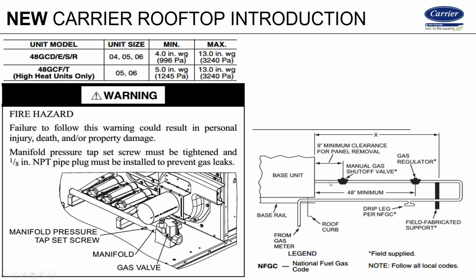When you put these regulators right next to the unit, in the winter when it's extremely cold, that exhaust, as the moisture freezes, it dissipates out and can fall right on top of the vent of the regulator. So you need to either keep your regulator out here or hook a tube up to the vent port and run that somewhere away from the exhaust from the unit. That goes for all units. Matter of fact, it goes for all manufacturers because a lot of us are the same.